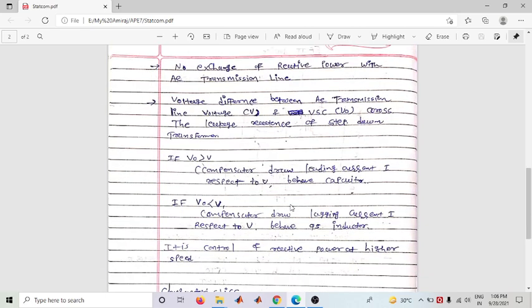The second condition is when V0 is less than V — meaning the transmission line voltage is higher compared to the converter voltage. In this case, the compensator draws lagging current with respect to voltage, and it behaves like an inductor, operating at lagging power factor.